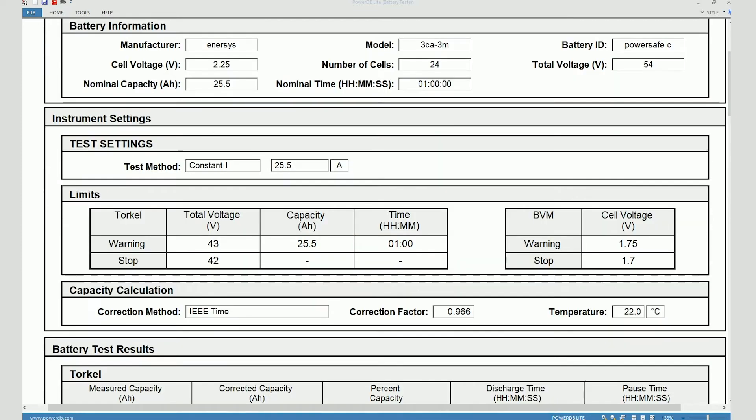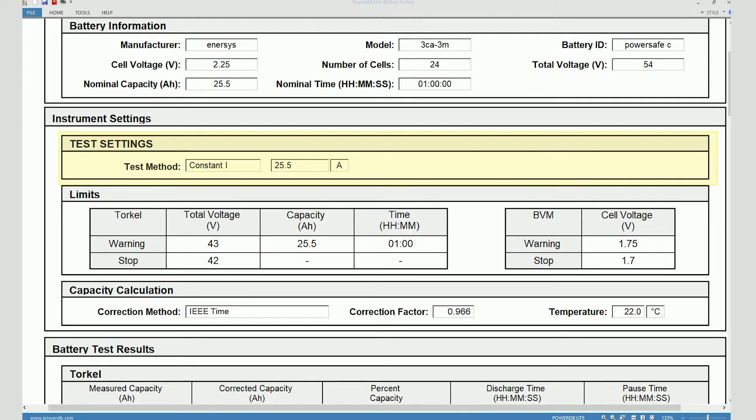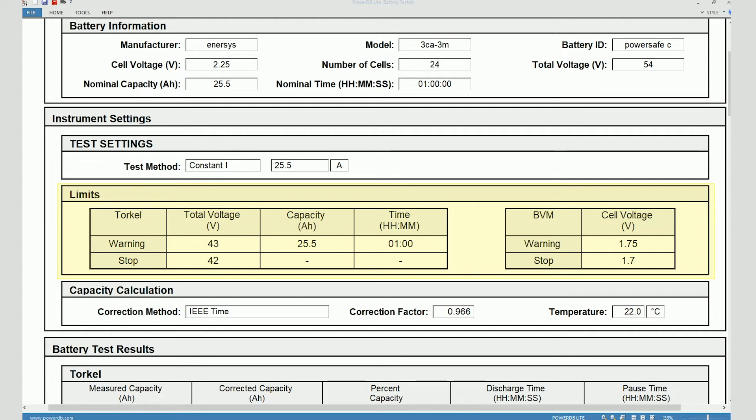Below that you can see the instrument settings which are basically the test settings that were made on the instrument before starting the test. That includes the test method which in this case was a constant current method and the test current which was selected which is 25.5 amps. The limits that were set on the instrument, the warning limits and the stop limits both on the Torkel and the BVMs.